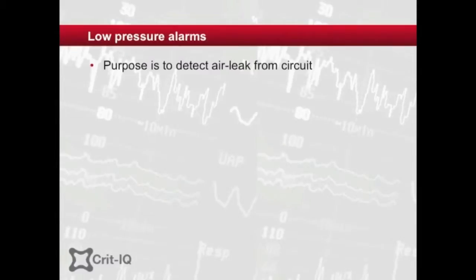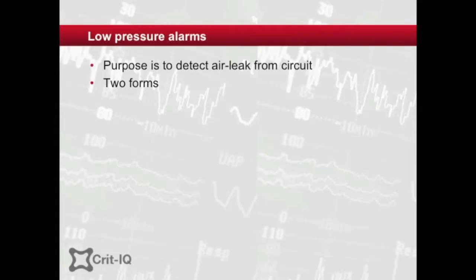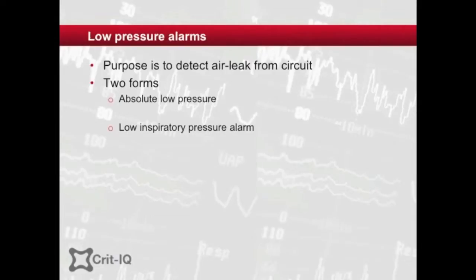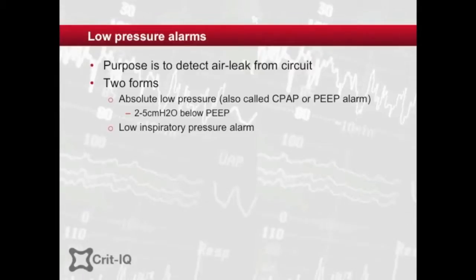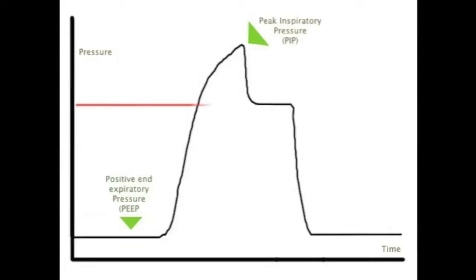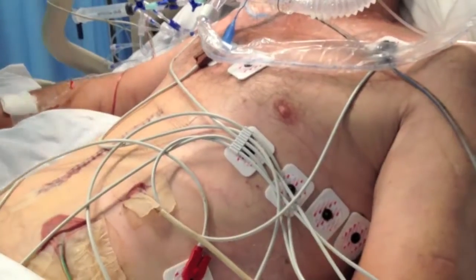The purpose of a low pressure alarm is to detect when air is escaping from the circuit to a degree that the circuit pressure drops. This can be either an absolute pressure or the inspiratory pressure. The former is sometimes known as a low CPAP or low PEEP alarm, with the threshold set to 2–5 centimetres of water below the set PEEP; failure to maintain this is a sign of a major leak. In the latter, the alarm can be set 5–10 centimetres of water below the expected peak, and failure to achieve this value suggests a major leak, including disconnection. Confirmation can be achieved by the loss of a capnograph trace and the failure of the chest to rise and fall.